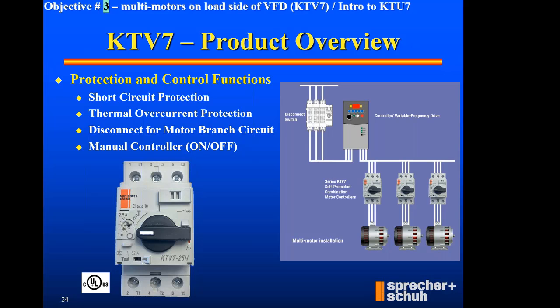So I'd be using a fuse block plus a thermal overload if KTV didn't exist. But okay, what does KTV offer us? Here are the protection and control functions of KTV. Hey, there's a magnetic armature on the inside of this KTV that gives us that short circuit protection that National Electric Code says is required. Also integral into the KTV is thermal bimetallic overload protection. So, hey, I just said I've got BCPD and I've got overload protection.